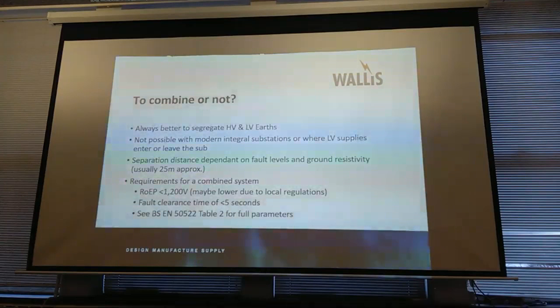So by virtue of you then pulling that HV transformer ring main unit into that LV environment, you don't have the isolation between the two. So if you don't have the isolation between the two, you've got to bond the two together for safety reasons. So therefore, you've got to take into account the rise of potential.